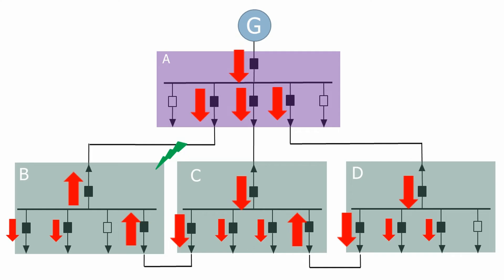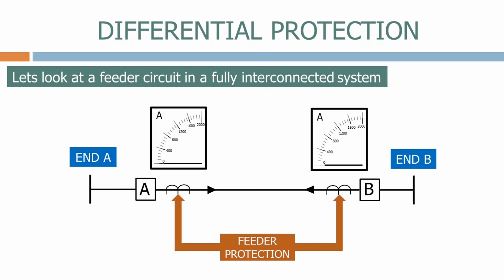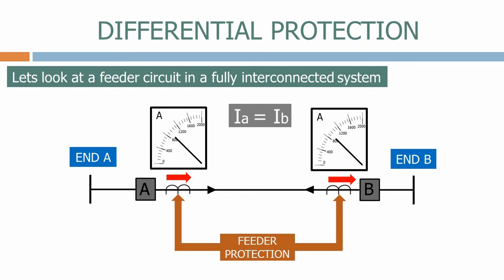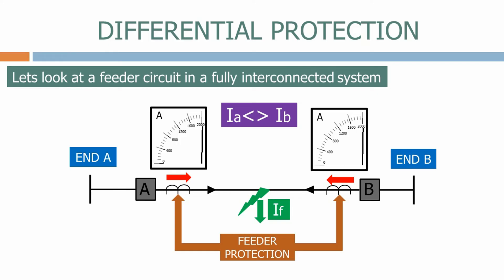Let's now look at our feeder again. With the circuit breakers closed, the currents at both ends A and B are the same and the feeder protection is stable. When we apply a fault on the feeder, because it's a fully interconnected system, the current magnitudes on both ends A and B both increase and the current on End B reverses direction as it feeds the fault from the rest of the network. The currents are no longer balanced on A and B, so the feeder protection detects this difference and trips the circuit breakers, clearing the fault from the system.